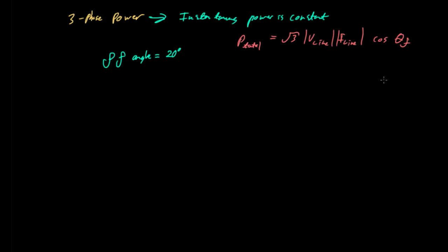So just to repeat some of the key equations that we'll make use of, I'll point these out as we go through them. So let's first start with the power factor. We have a power factor of 0.78. So we can compute the angle that corresponds to that power factor. And then from that we can compute the sine of that angle. We'll need this to deal with the reactive component of the power. So if the power factor is 0.78, the sine of theta is going to be 0.626, just a basic trig property. So if sine of theta is 0.626, then the reactive component of that power is going to be our 24 megawatts times sine of theta, or 15 megawatts. The active component of the power is going to be 18.7 megawatts, 24 times cosine of theta. That shows you directly how the power factor plays into these calculations.